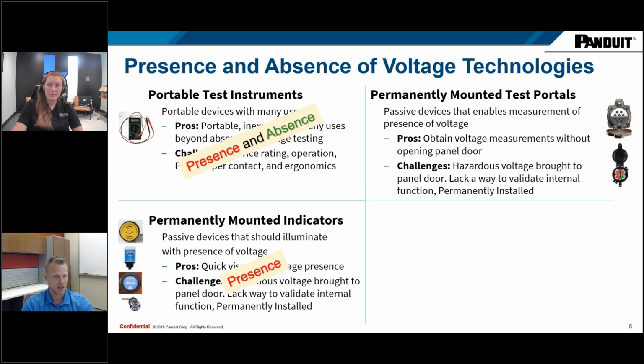Other challenges is just like the indicators, the hazardous voltage is brought to the back of that device, which is on the door. So you're bringing the hazardous voltage to the door. And again, just like indicators, they lack a way to validate that the function of that device is still working, right? You can't verify that it's connected properly. You can't verify that it's functioning properly still. And then just like indicators, permanently installed. So if you want to be able to have that measurement point on the outside of the panel in multiple places, you've got to install multiple of these devices. Again, because you can't verify that the device is working properly. Really just great for presence of voltage, absence of voltage, not so much.